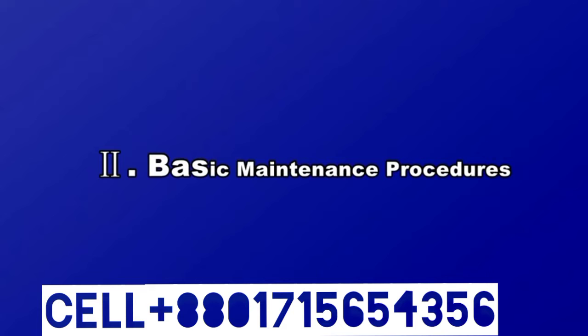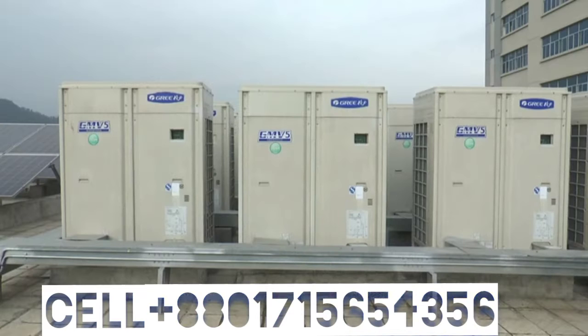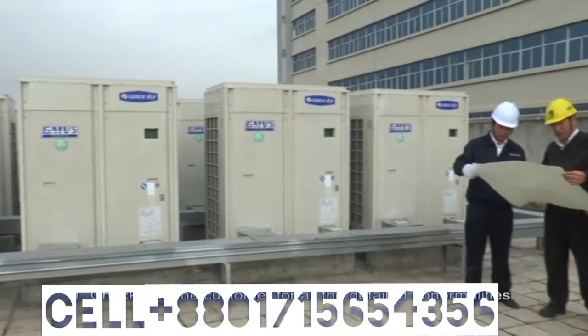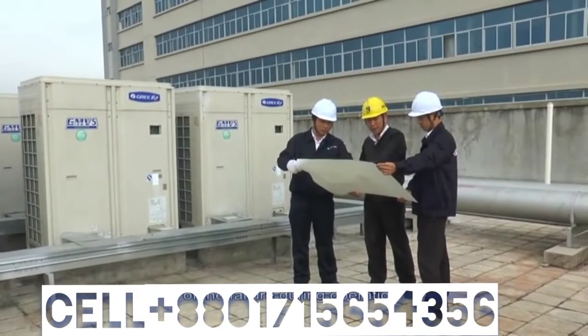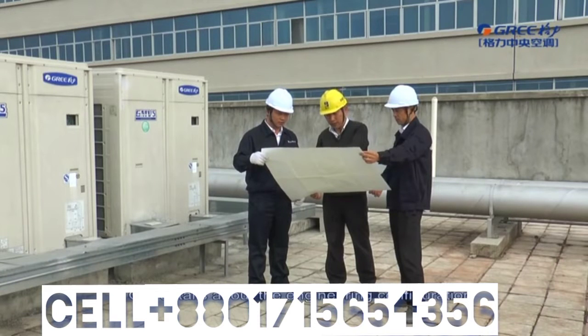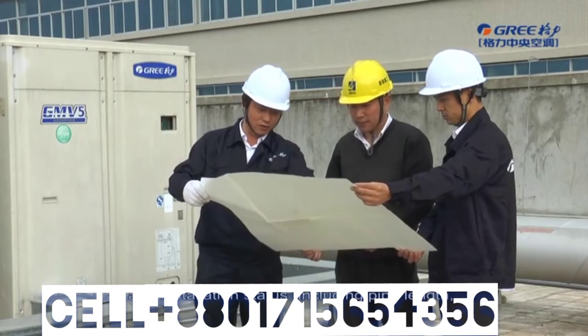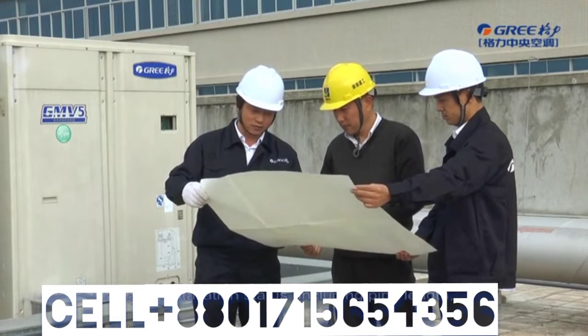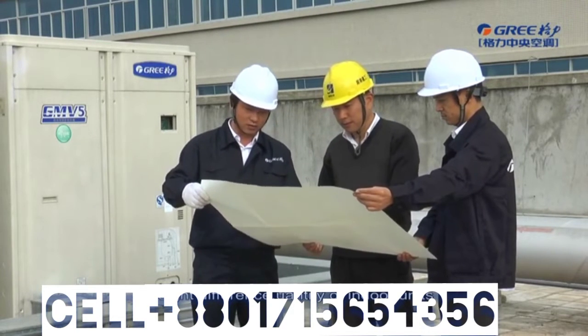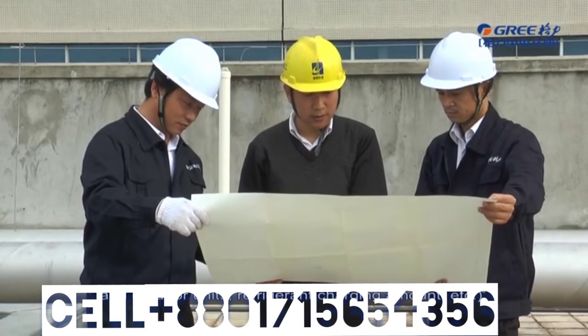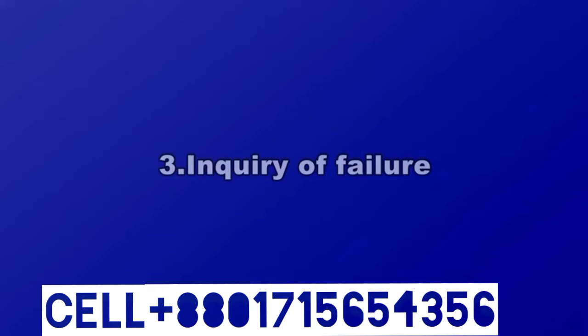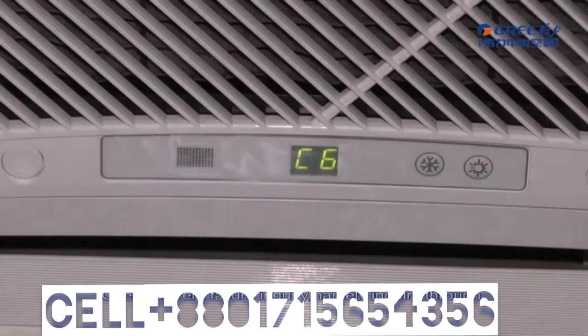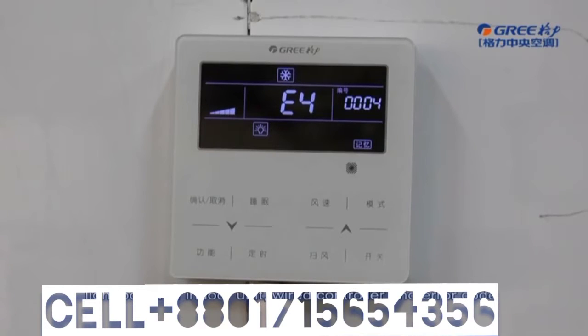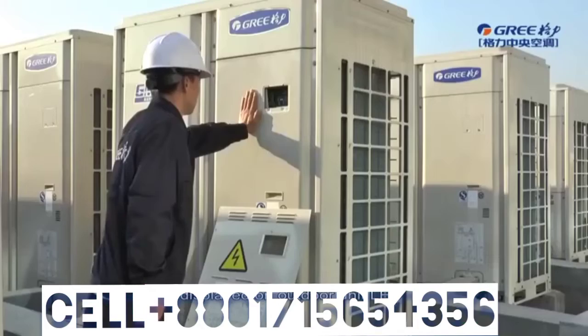Part 2 Basic Maintenance Procedures. First, check with the customer for all the detailed abnormalities of the failure during operation. Second, get details about the engineering configuration and installation status, including pipe length, height difference, quantity of indoor units and outdoor units, refrigerant charging amount, etc. 3. Inquiry of failure. There are 2 methods of failure inquiry. One is current failure inquiry, namely inquiry through light board of indoor unit, wired controller, and error code displayed on outdoor unit's LED.